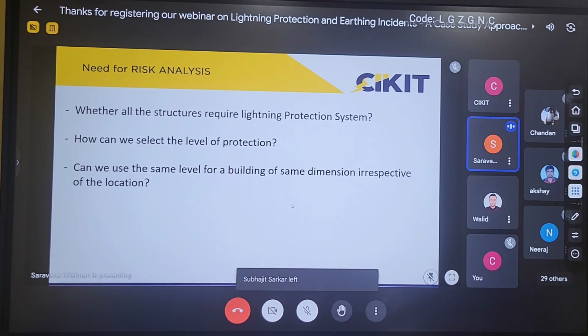These are the commonly asked questions by many people related to the risk assessment. First one is whether all the structures require lightning protection system or not. Second, how can we select the suitable level of protection? And third one is how can we use the same level of protection for buildings at different locations? For example, if I take the same building of height 15 meters, if the building is located in Chennai, Mumbai, and another building of the same dimension is located in Bhubaneswar, whether the level of protection will be the same for the buildings of same dimensions in different locations. These are the commonly asked questions by many people.